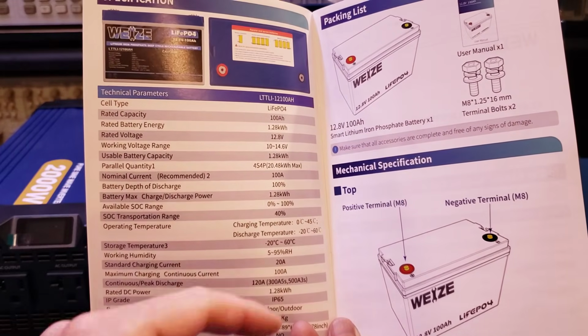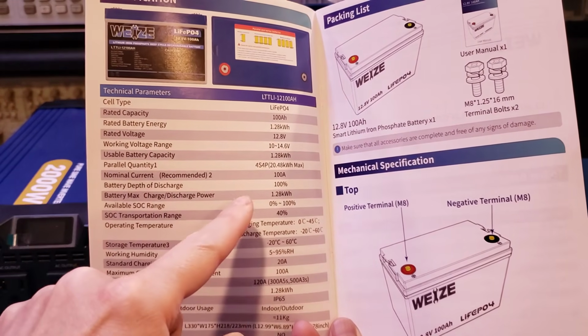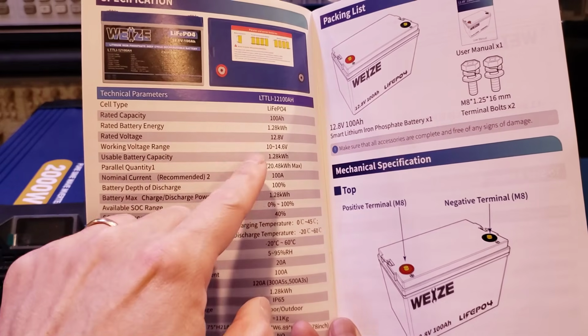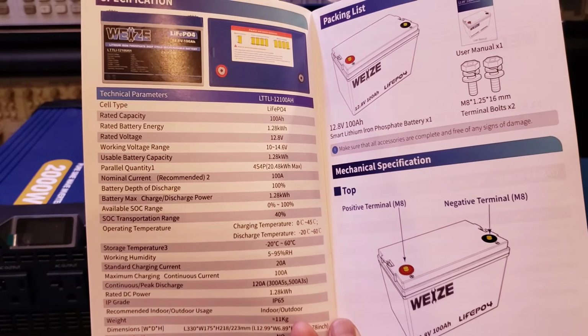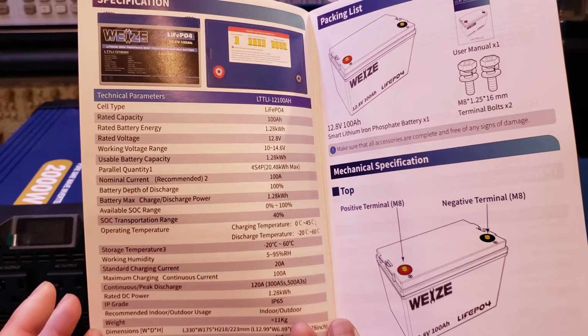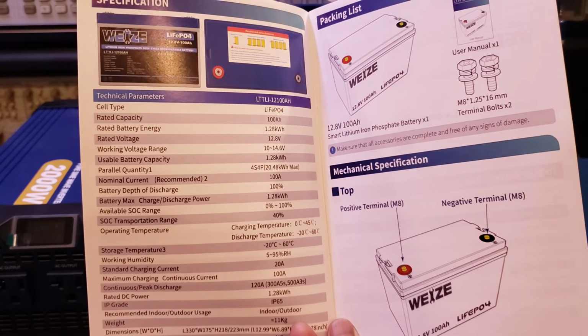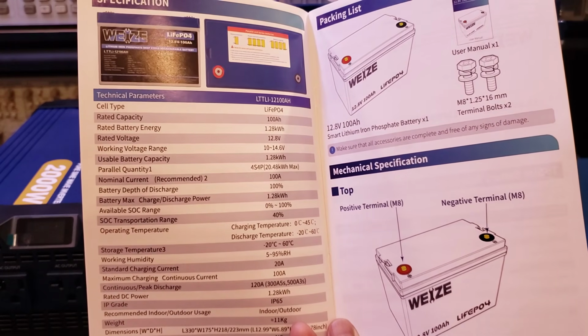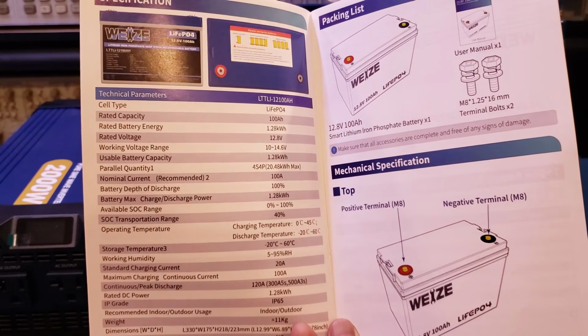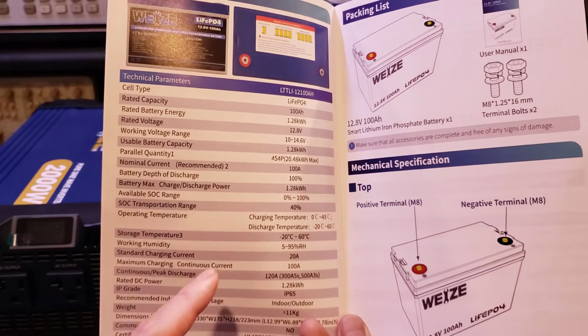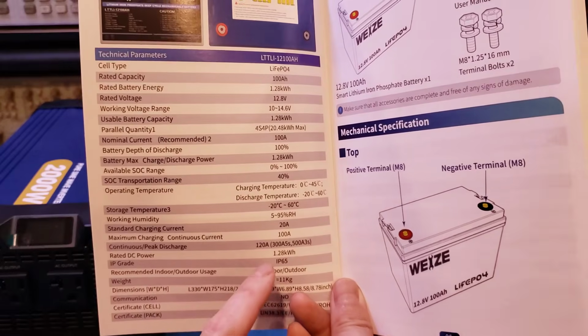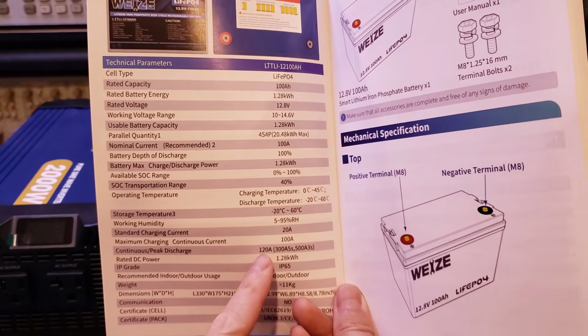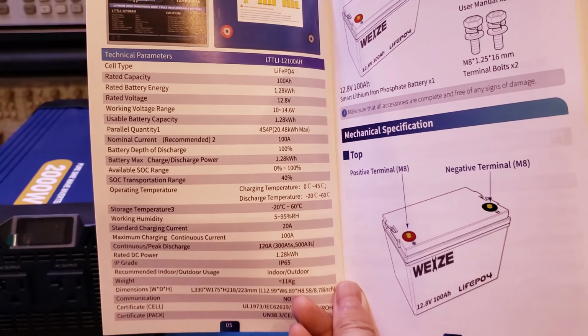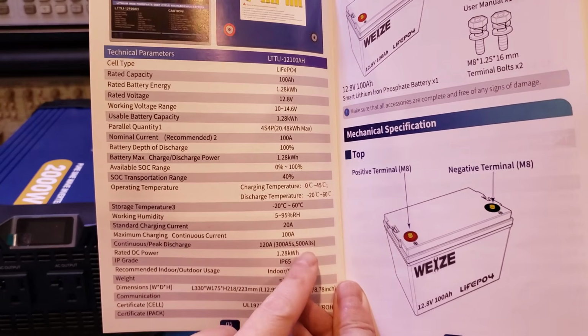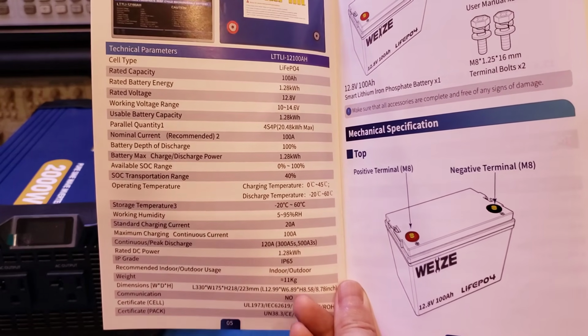Here you can see that the capacity of the battery is 100 amp hours, and the maximum configuration is 4S4P. So that's 4 in series and 4 in parallel, with a total of 16 batteries. Now this is very similar to most of the 12 volts LFP batteries. The maximum continuous discharge current here, you can see, is rated as 120 amps, with a peak current up to 500 amps for 3 seconds. Of course, 300 amps for 5 seconds.